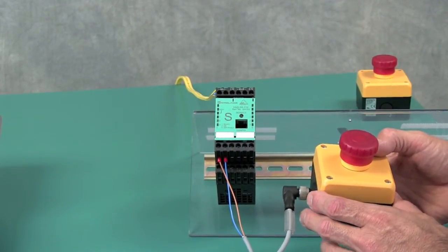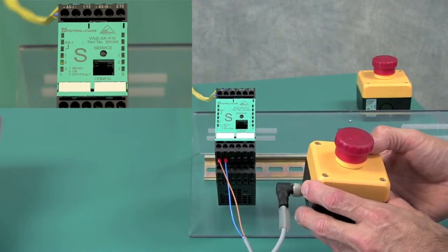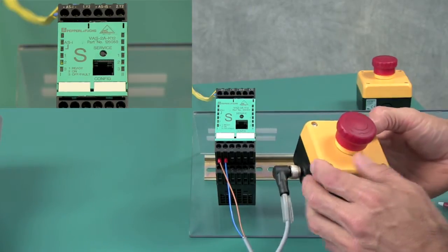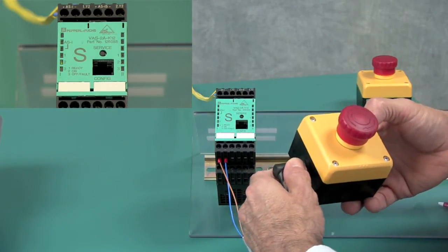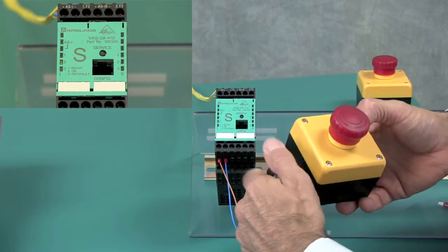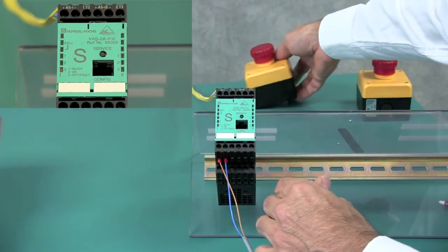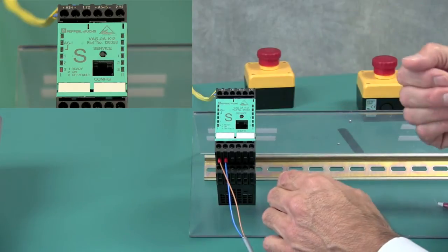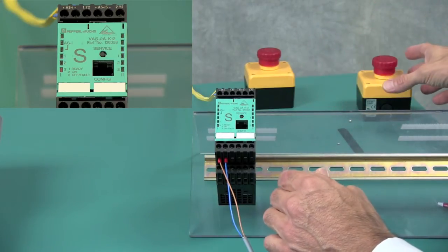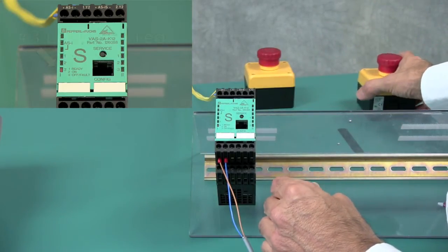Let's start by going through the procedure for the K12 safety monitor. The way I create the fault is by simply disconnecting my e-stop. As required, the safety system goes to a shutdown and the number 3 LED illuminates red.